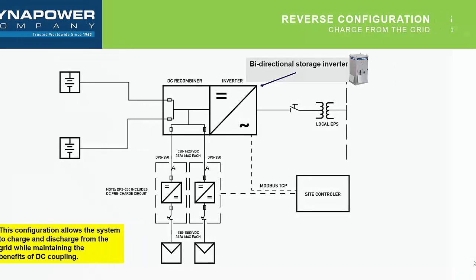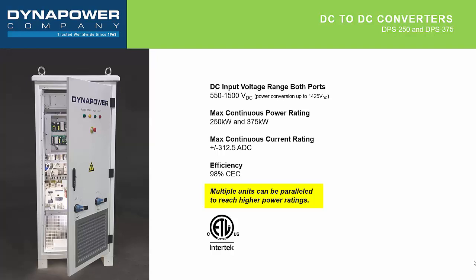So let's talk a little bit about the Dynapower specific converters that are applicable and available on the market today. The Dynapower DPS 250 and the DPS 375 are both UL listed converters. They have an input voltage range of 550 up to 1500 volts DC. That's both on the input side, that is the battery side, as well as the PV bus side, with an estimated CEC efficiency of 98.2%. And again, these can be run in parallel so that you can get the optimal size all the way up to potentially 3 megawatts behind a single PV inverter.